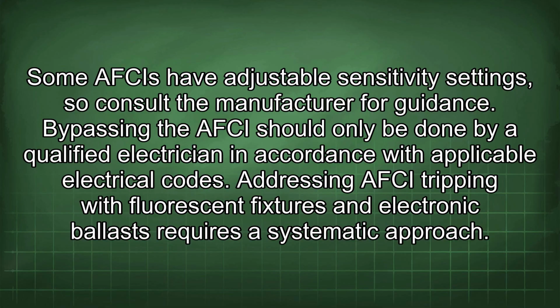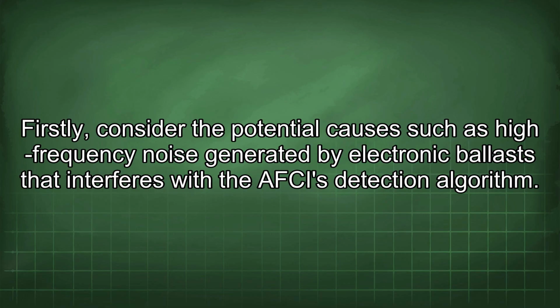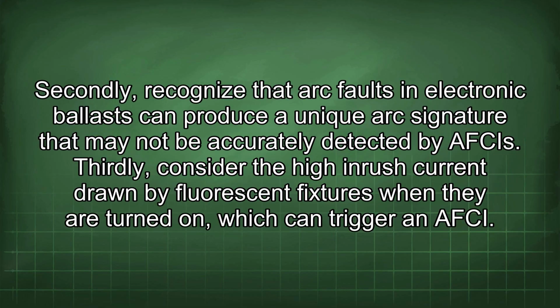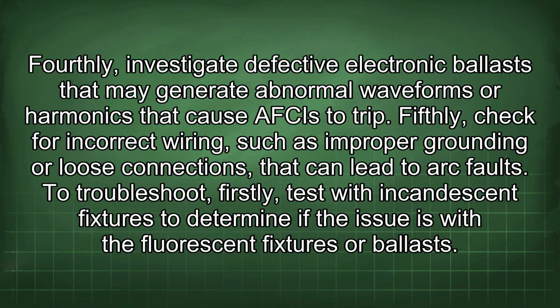Addressing AFCI tripping with fluorescent fixtures and electronic ballasts requires a systematic approach. Firstly, consider the potential causes such as high-frequency noise generated by electronic ballasts that interferes with the AFCI's detection algorithm. Secondly, recognize that the arc faults in electronic ballasts can produce a unique arc signature that may not be accurately detected by AFCIs. Thirdly, consider the high inrush current drawn by fluorescent fixtures when they are turned on, which can trigger an AFCI. Fourthly, investigate defective electronic ballasts that may generate abnormal waveforms or harmonics that cause AFCIs to trip. Fifthly, check for incorrect wiring, such as improper grounding or loose connections, that can lead to arc faults.